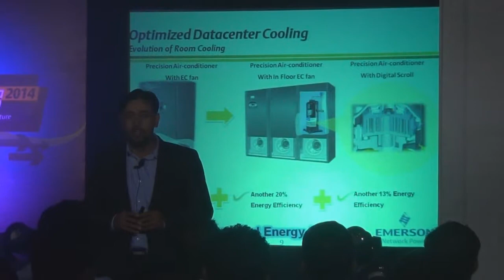We moved from a traditional belt-driven system to precision ACs, then to EC fan technologies. The latest upgradation in the industry is moving from a normal scroll to a digital scroll — you can see on the right side, we have here integrated in-floor EC fans. Overall, this integration — the change from a normal precision AC to digital scroll EC fan, the digital scroll compressor, and the in-floor type EC fan — gives a power consumption difference of about 35% minimum over a precision AC with fixed scroll and EC fan. We'll talk in detail about this in the next slides.